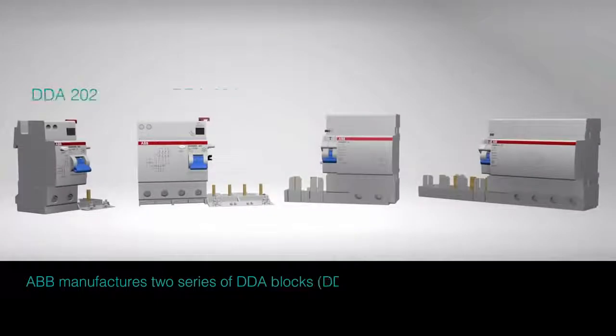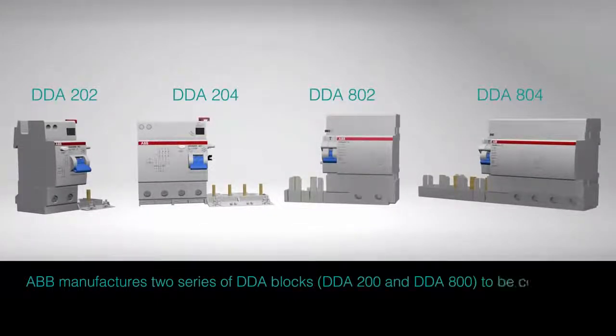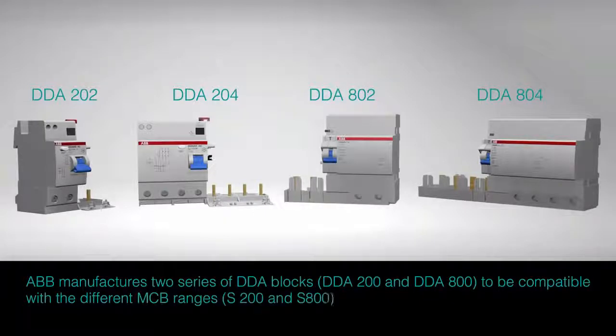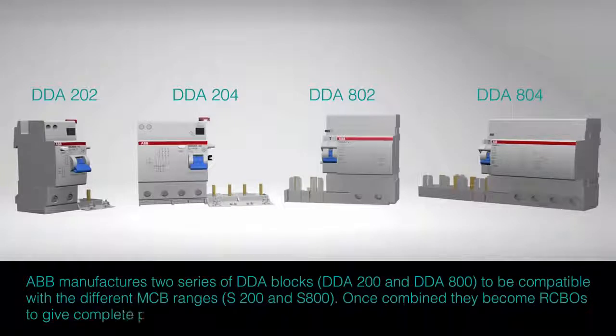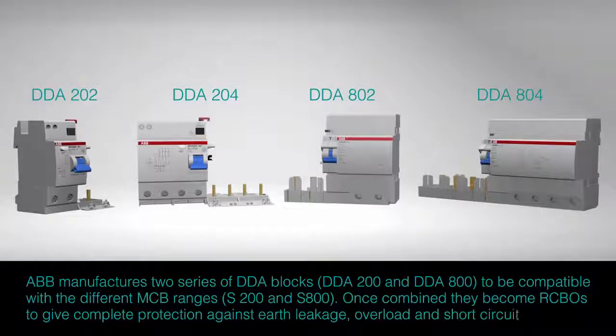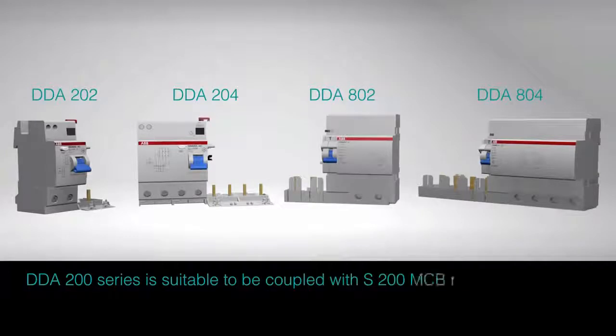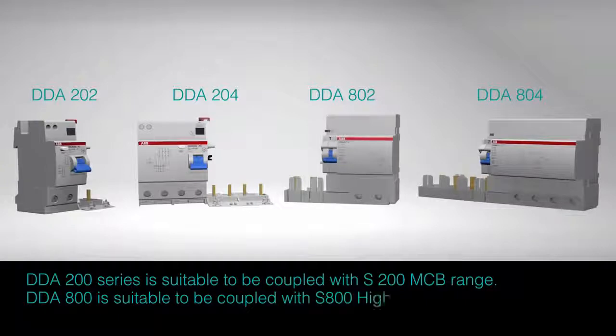ABB manufactures two series of DDA blocks, DDA 200 and DDA 800, to be compatible with the different MCB ranges, S200 and S800. Once combined, they become RCBOs to give complete protection against earth leakage, overload and short-circuit faults. DDA 200 series is suitable to be coupled with the S200 MCB range. DDA 800 is suitable to be coupled with the S800 high-performance MCB range.